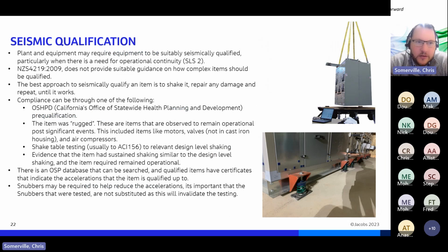Seismic qualification - with some buildings, plant and equipment may need to be specified as seismic qualified. Currently, especially for SLS2 buildings where operational continuity is required, you generally need seismic compliant equipment. But the issue is that 4219 doesn't actually have a suitable way of providing guidance on that.